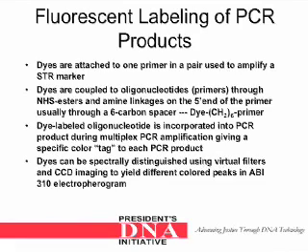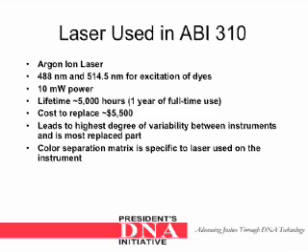Dyes can be spectrally distinguished using virtual filters and CCD imaging to produce different colored peaks in the ABI 310 electropherogram. The laser used in the ABI 310 is an argon-ion laser with wavelengths between 488 nanometers and 514.5 nanometers for excitation of dyes. It has 10 milliwatt power and a lifetime of approximately 5,000 hours, which is one year of full-time use, with a replacement cost of about $5,500. It leads to the highest degree of variability between instruments and is the most replaced part. Color separation matrix is specific to the laser used on the instrument.